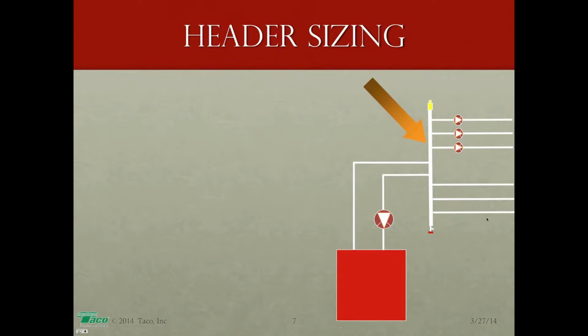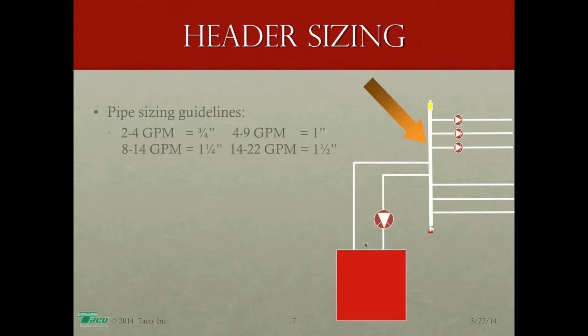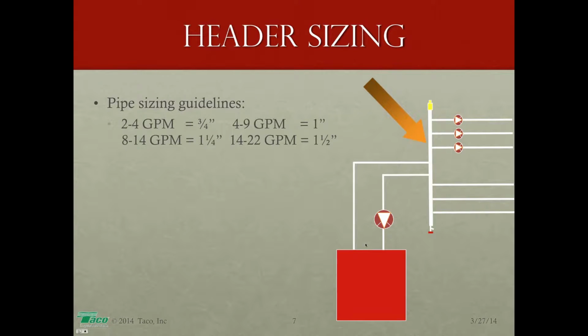Header sizing. So we've done the boiler pipe sizing thing. It's follow the instructions. Now to size the header, the antler part of the moose antler piping. On the face of it, you would follow standard hydronic pipe sizing guidelines. If the flow rate required for your distribution is 2 to 4 gallons per minute, 3/4 inch copper is fine. 4 to 9 gallons a minute, 1 inch copper is fine. 8 to 14, 1.25 inch, or 14 to 22 gallons per minute, 1.5 inch.